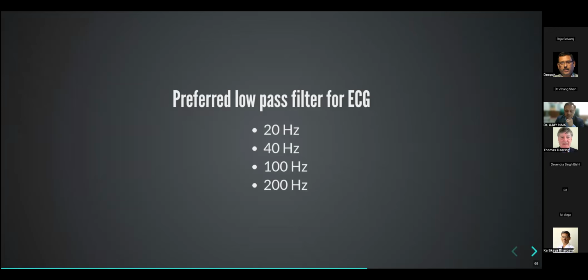Okay, so I think it's sort of equally divided between 40 and 100, which is fine. There are basically two schools of thought, but at least you should know the compromise that you are making with each of these. Now, 100 hertz is better in terms of diagnostic ECG quality. So if you want to see the QRS well, you want to see the notches, and you want to see the waveforms clearly, 100 hertz is better. 40 hertz is better in terms of reducing noise because you don't even need a notch filter. Even the AC noise is cut off inside that. So your noise will be less. You'll have a cleaner ECG, but you cannot use it very well for morphology, and morphology can be misleading.